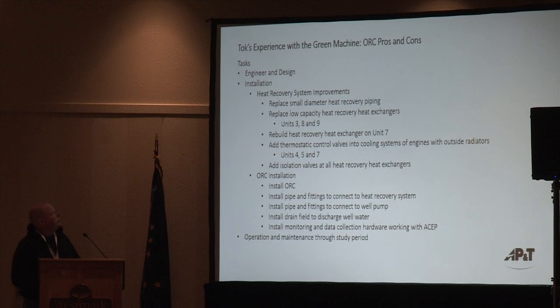Our scope of work included engineering and design for installing the green machine in Tok, plus installation and construction: replacing the small diameter heat recovery piping in the power plant, replacing the low capacity heat recovery heat exchangers, rebuilding a heat exchanger, and adding thermostatic control valves on units with external radiators. We also added isolation valves throughout the piping system so we could more efficiently run the heat recovery system for the best performance of the green machine.